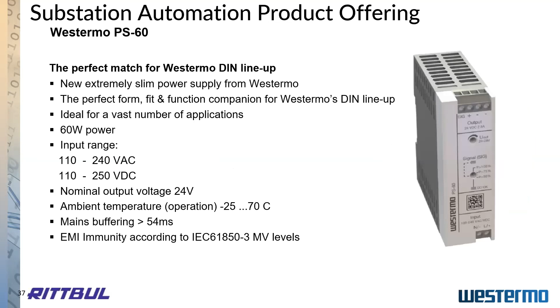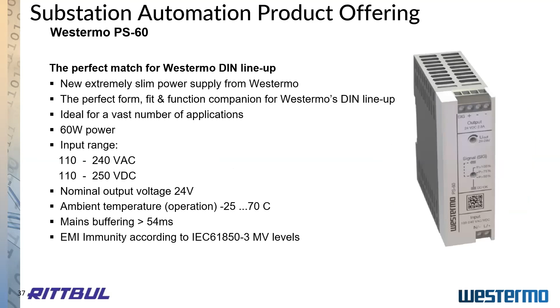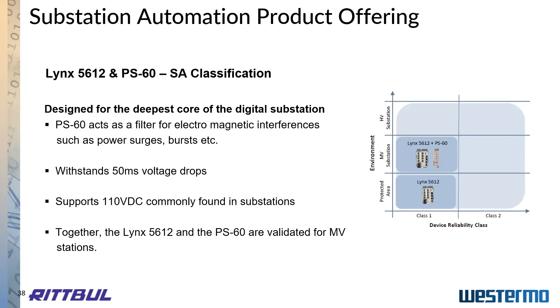We have also introduced a power supply, the Westermo PS60. It is isolated and 61850 approved as well. In combination with the Lynx, it forms a package providing input ranges between 110 and 240 VAC, with a normal output voltage of 24 volts. So we have the complete package for medium voltage and protected areas, with the PS60 and the Lynx 5612. Together they withstand 50 millisecond voltage drops that may sometimes appear, and support 110 volts DC, commonly found in substations as well.